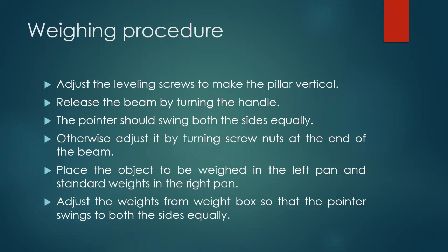If the pointer moves more towards the left, the object to be weighed is heavier than the standard weights, so we must increase the weight on the right pan. If the pointer moves more towards the right, the standard weight is more and we must reduce it. When checking for accuracy, we keep the weights constant on the right and increase or decrease the quantity of the object depending on how far the pointer is moving on either side.